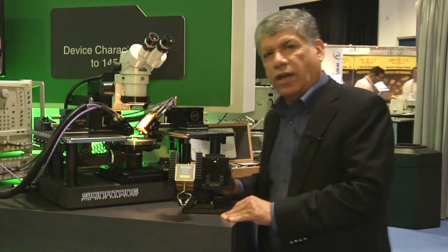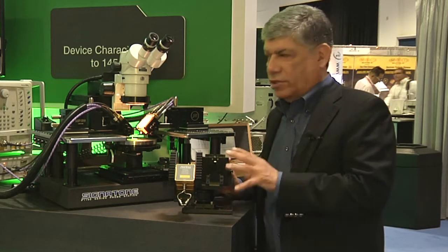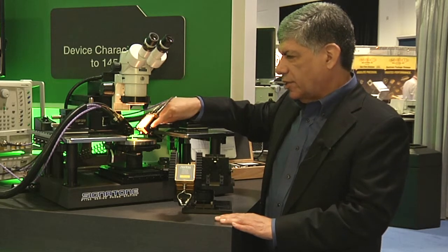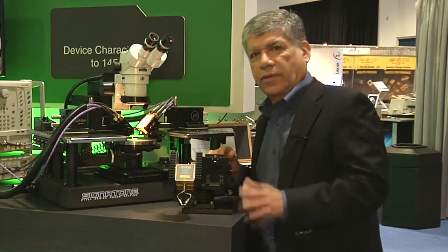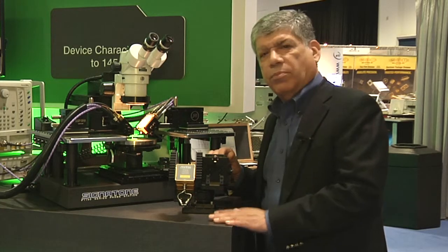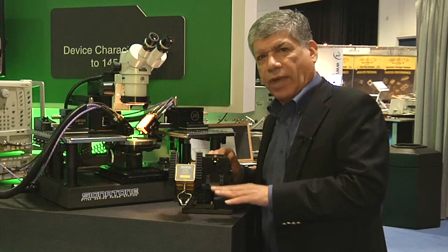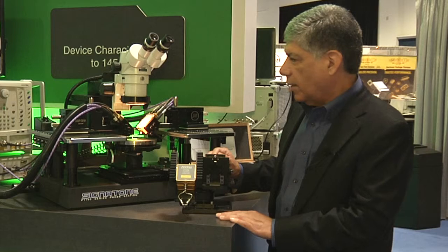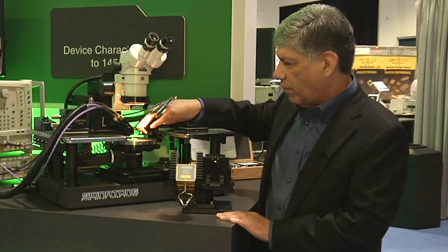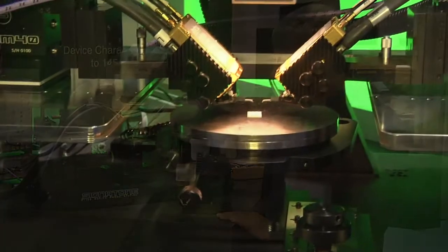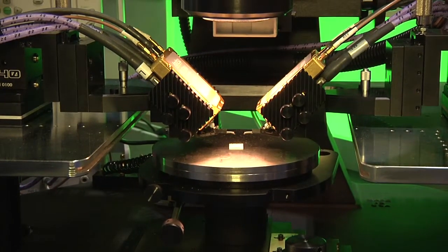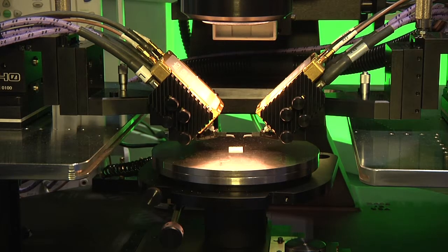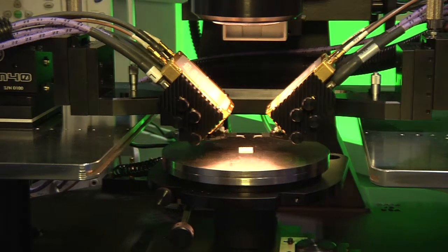So that's why when we developed the 145 gigahertz modules and total system, we also were working with probe station people and probe vendors in order to provide the probes at the same time as we were showing the modules and providing the modules. So that's what we have here, is we have a direct connect to a GGB probe going to 145 gigahertz using their standard substrate and characterizing the system up to 145 with better than coax accuracy.